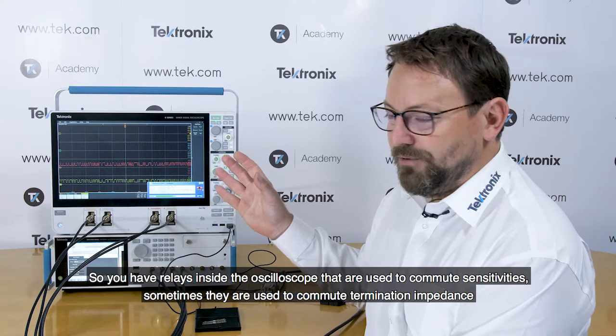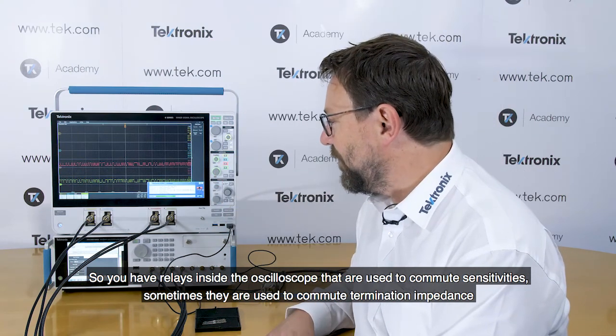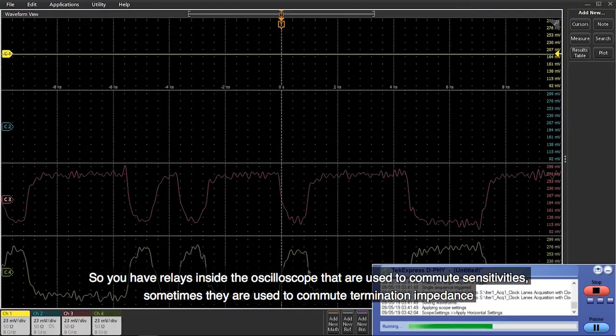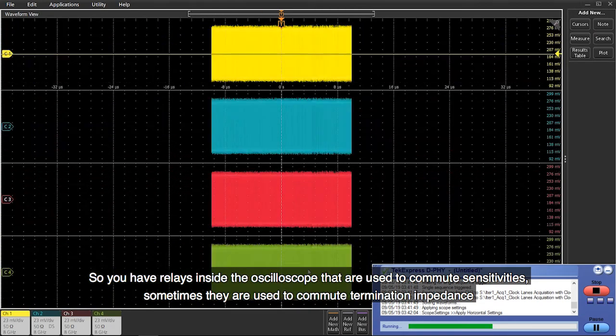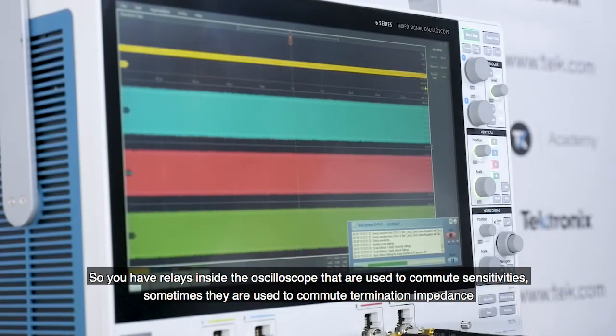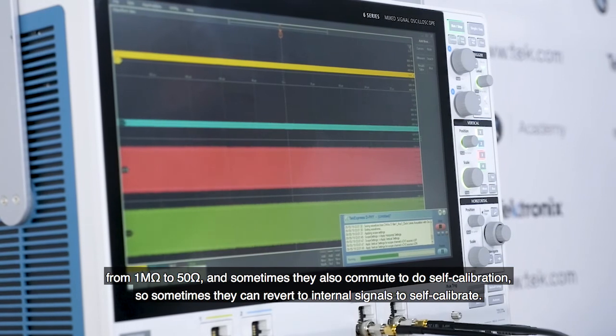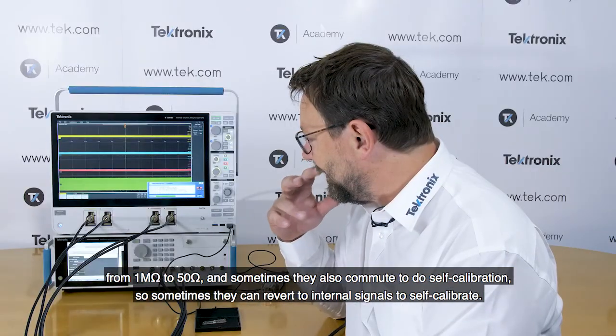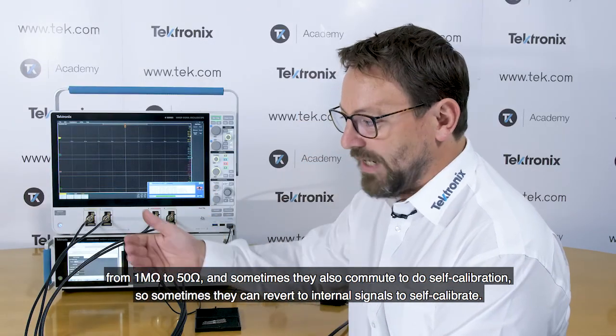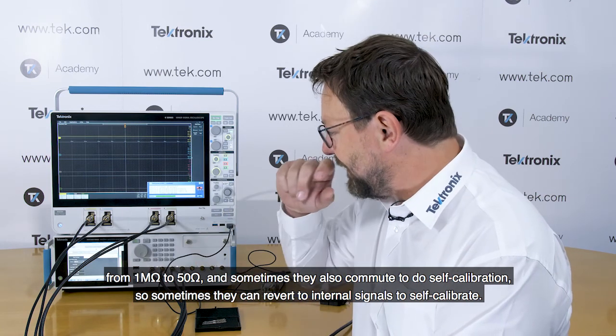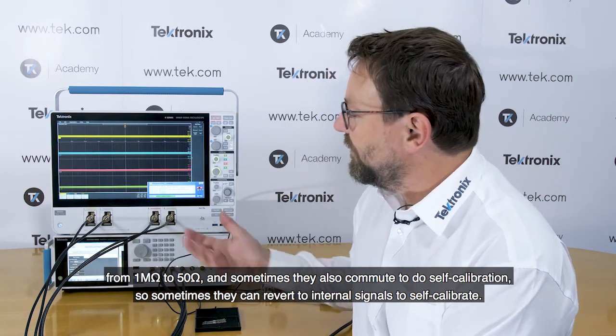So you have relays inside the oscilloscope that are used to commute sensitivities. Sometimes they are used to commute termination impedance from 1 megohm to 50 ohm. And sometimes they are also commuted to do self-calibration. So sometimes they can revert to internal signals to self-calibrate and come back to the outside signal.